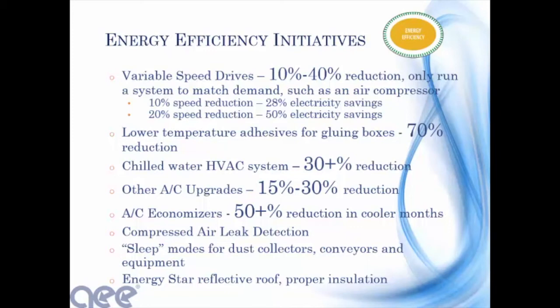Compressed air leak detection. I mentioned earlier that compressed air is notoriously inefficient. Only 15 to 20% of the electricity that goes into that compressor actually makes air, and then typically you have a leak rate anywhere from 10 to 30%. So you're not very efficient to begin with, and then you end up wasting upwards of a third of your air. If you can have a good leak detection program to keep that leak rate down, you'll save a lot of money. Apparently, the rule of thumb is even a well-maintained plant with a good leak detection program still has about a 10% leak rate.